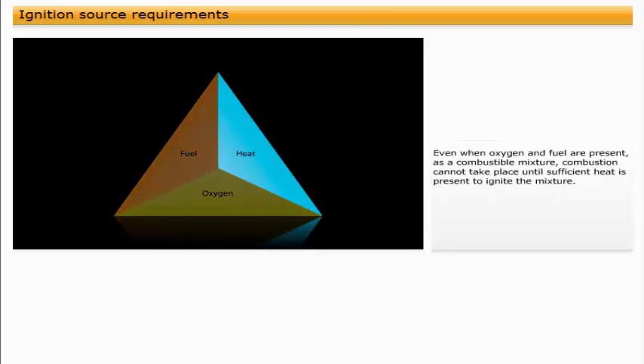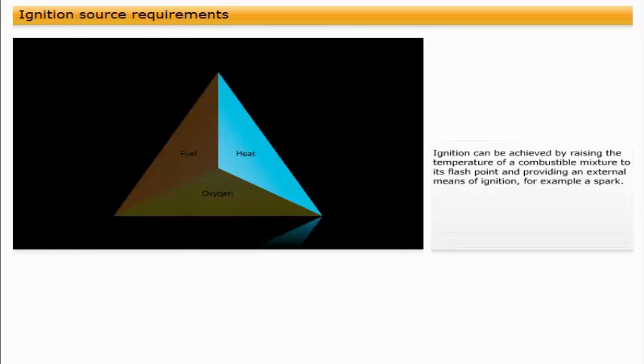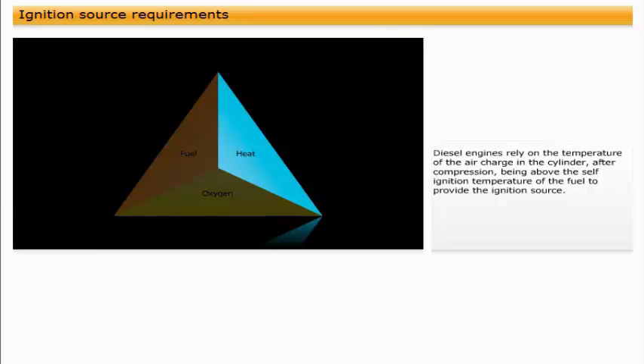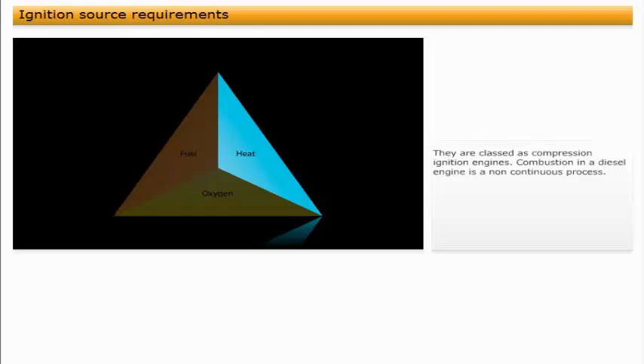Even when oxygen and fuel are present as a combustible mixture, combustion cannot take place until sufficient heat is present to ignite the mixture. Ignition can be achieved by raising the temperature of a combustible mixture to its flash point and providing an external means of ignition, for example a spark. Ignition can also be achieved by raising the temperature of the mixture above its self-ignition temperature. Diesel engines rely on the temperature of the air charge in the cylinder after compression being above the self-ignition temperature of the fuel to provide the ignition source. They are classed as compression ignition engines.